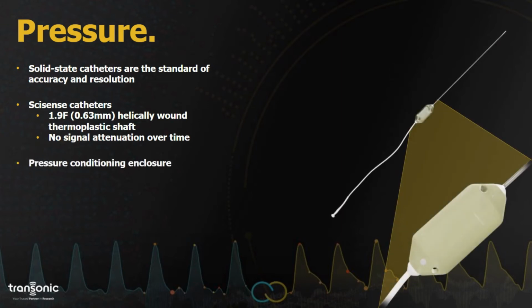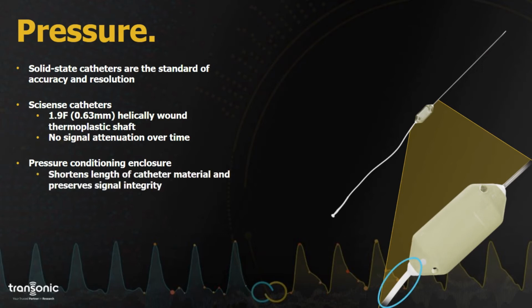As well, what you'll notice, and I referenced earlier, is this interesting design. It's a pressure conditioning enclosure that's actually located roughly halfway up the catheter. So this is an important differentiator. It's a feature, not a bug. It plays 2 important roles. What it does is it shortens the length of the actual catheter material that's required to be inside the animal. One of the challenges with some other designs is that you have this very sensitive catheter material the entire length of that shaft from the connector all the way up.